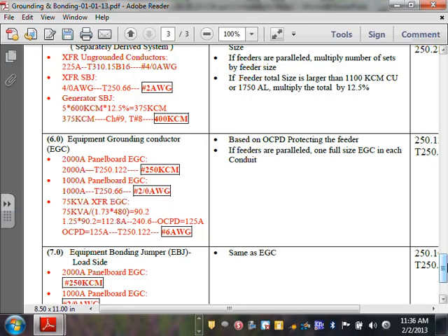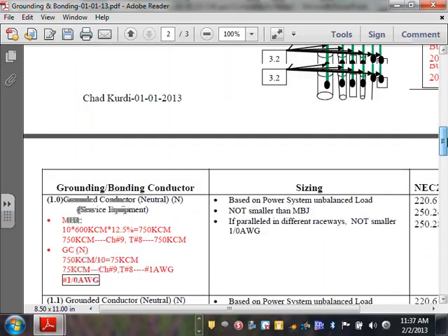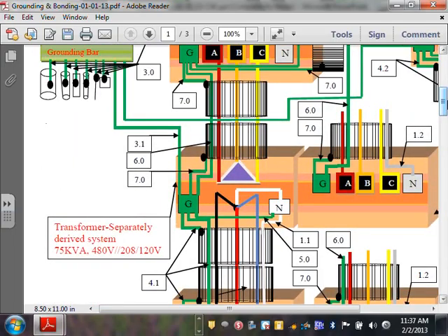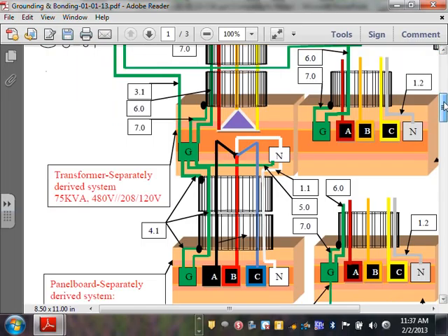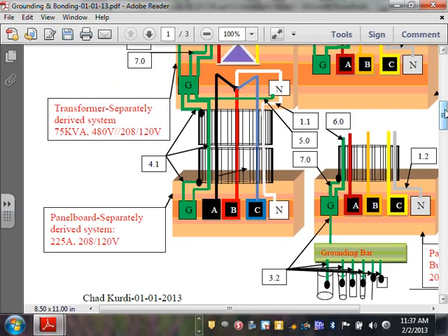So we sized number 6, the equipment grounding conductor. Okay, so coming here, my friends, I have my system bonding jumper, my equipment grounding conductor, my equipment bonding jumper load side here, and my grounding electrode conductor on the primary of the transformer, right? Very clear, right? Makes sense? Now we're going to go to the secondary of the transformer. I'm going to jump into the secondary of the transformer, if you don't mind. On the secondary side of the transformer, I have my neutral, and I showed you guys how we size that neutral. I have my 3-phase 208/120 coming in.